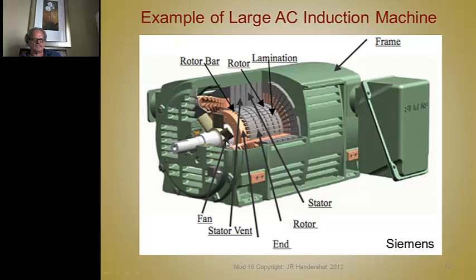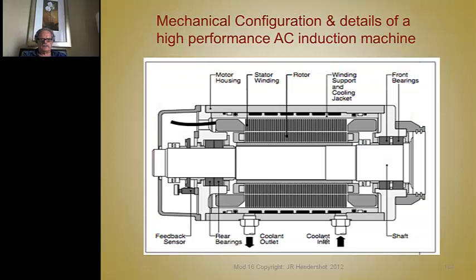But there's also a fan in here that helps focus, sucks the air through these louvers that forces it to go inside this end ring and be thrown out by these blade effects of the extended bars to cool not only the rotor but the stator as well. This is courtesy of Siemens.